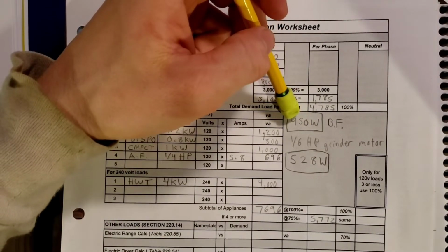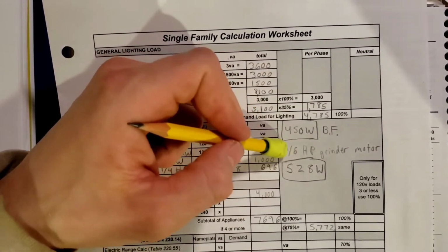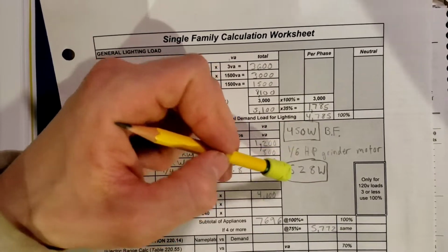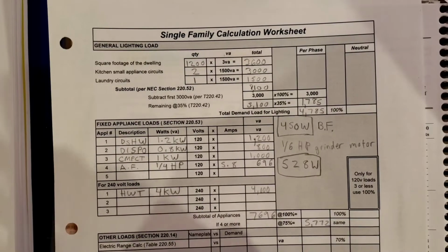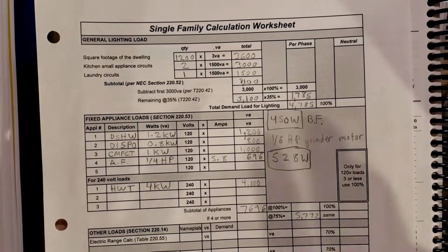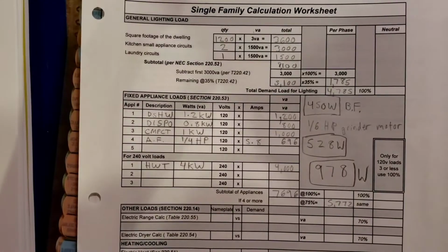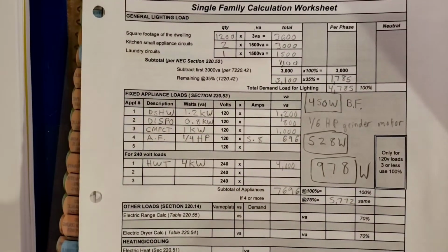Okay, so now that we already were given before our bathroom fan wattage on that paper, it literally just gave us the answer. So we had our 450 watts, since that was under the 500, it's here. And then, quarter or less, so that's why this is here too. We just did 528, so now we have both of our watts. Let's add them together, and this will be our answer for our not demand factor of anything. We're going to do this at 100%. There's no demand factor. We're not taking anything off. Okay, so for that one, we have 978 watts.